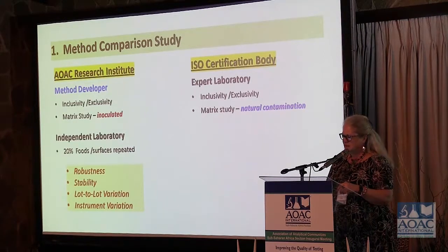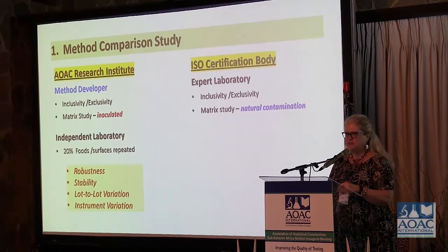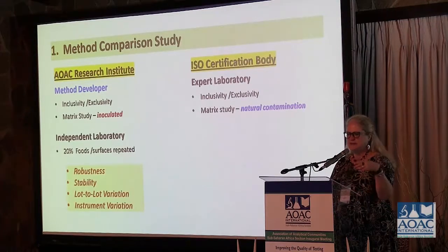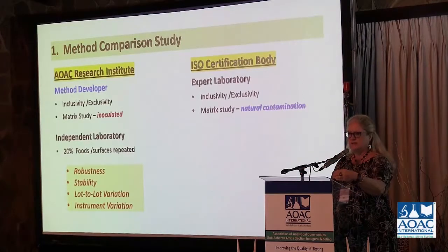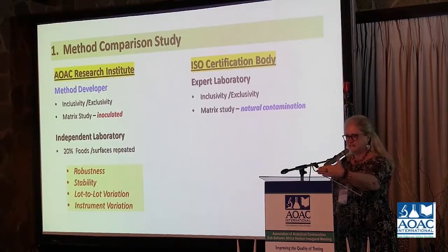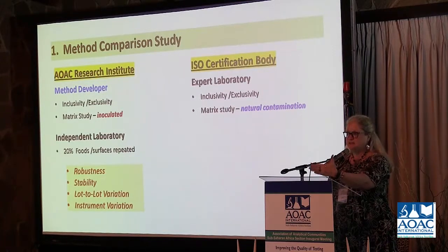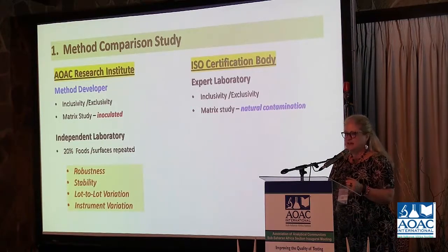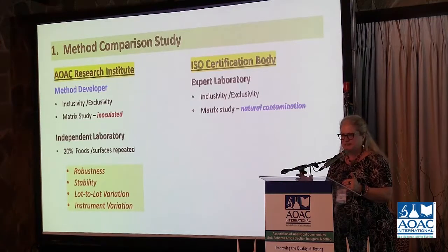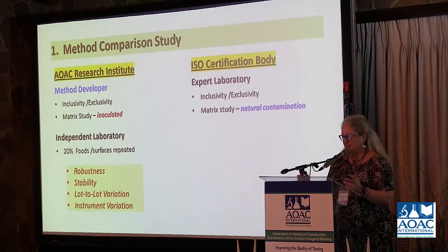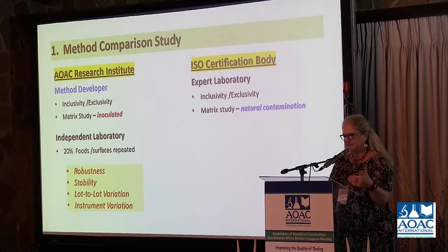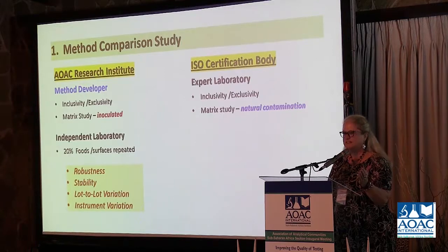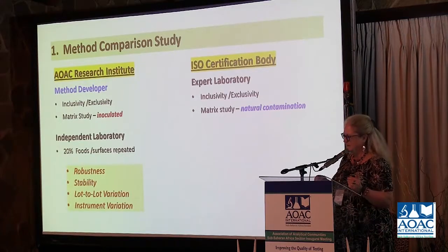Stability is looking at, if we have an expiration date of 2 years, we need to test product that's just made, a test kit, a product that's at the end of its shelf life, and then a product in the middle of the shelf life to show that, yes, I'll get that same result regardless, and the 2-year expiration date is correct because the method works the same. And then lot to lot, so each time it's manufactured, is the manufacturing process robust enough that you can expect that you get the same method made the same way. So we have to test different lots of the product and of instruments, if instrument is part of the method.